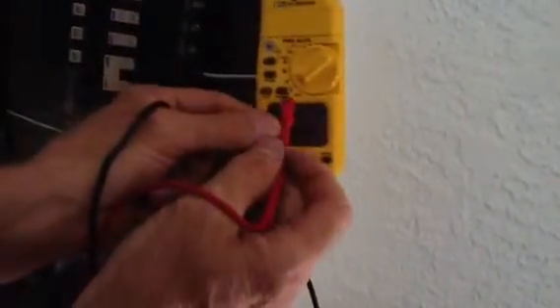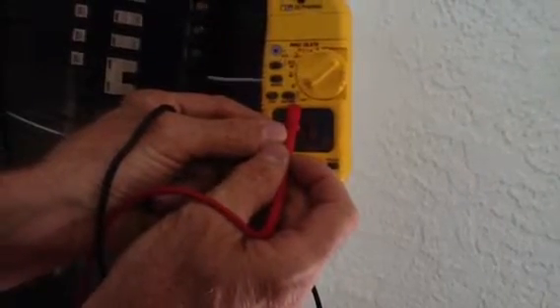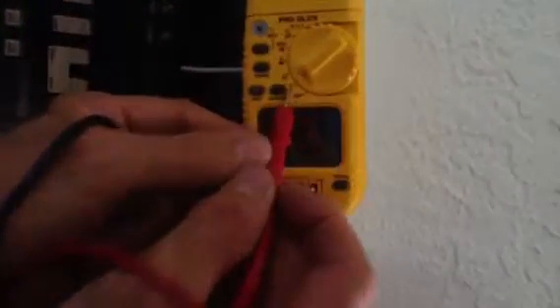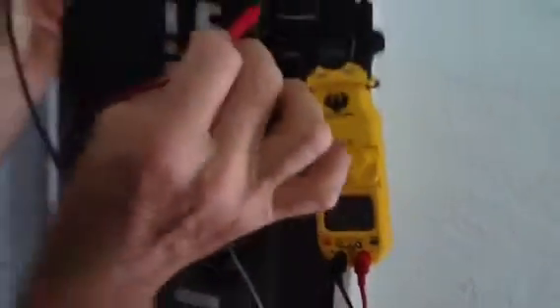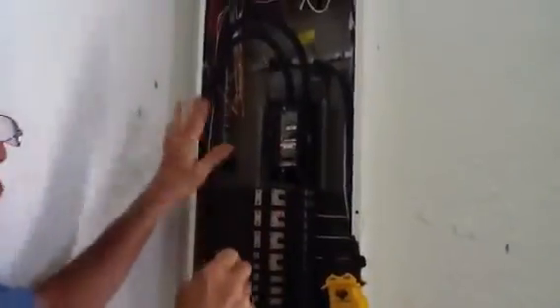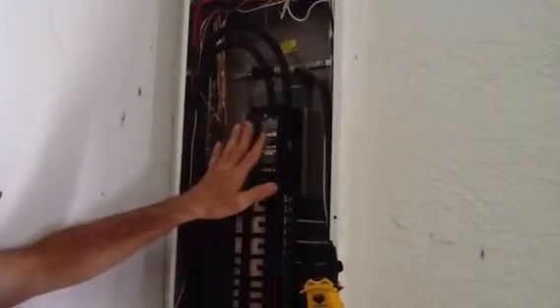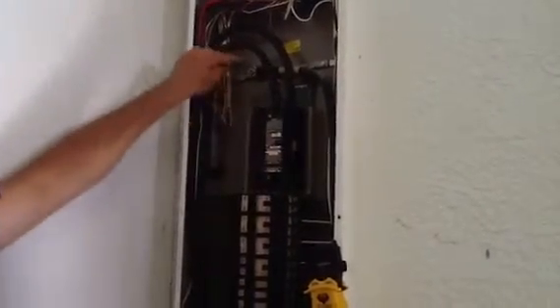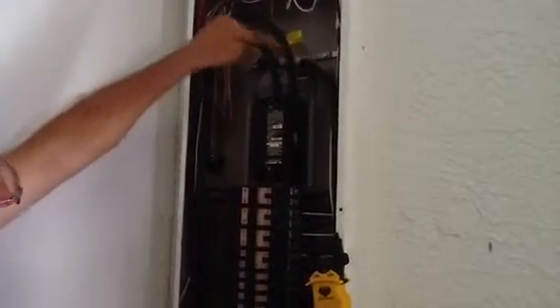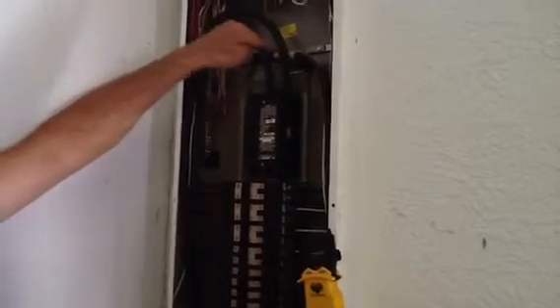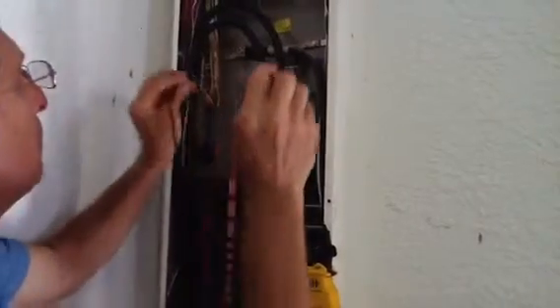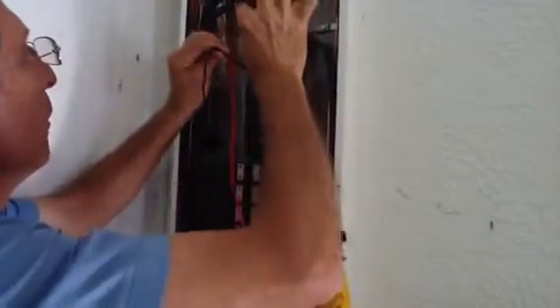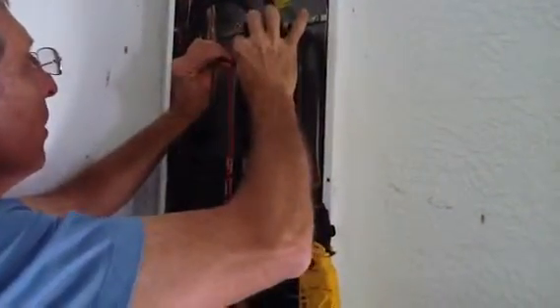It's off now. I'm going to set it on voltage. You see these little lines? This stands for AC voltage. See how that line's curved? Okay. Now, I'm going to take the two probes, and I'm going to put them, you see these two wires coming to the top of the breaker box? This is your 240 volts. This is your neutral. Your neutral will normally have a white wire marked on it, or white tape. So I'm going to put the probe on the 240 volts at the top of the breaker.